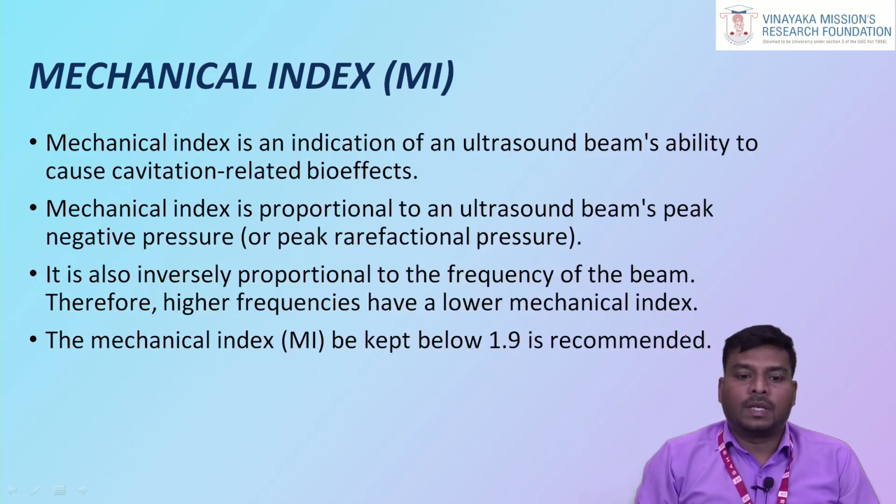Mechanical index. Mechanical index is proportional to the ultrasound beam's negative pressure or peak rarefaction pressure. Mechanical index is an indication of the ultrasound beam's ability to cause cavitation-related effects. Before, we discussed cavitation effects. It is also inversely proportional to the frequency of the beam. Therefore, higher frequencies have a lower mechanical index. Keeping the mechanical index below 1.9 is recommended.